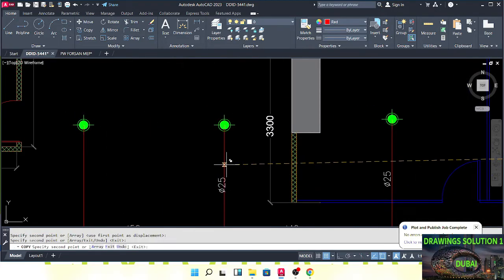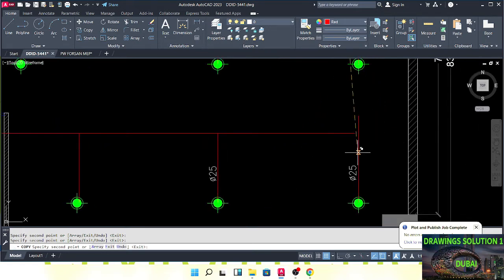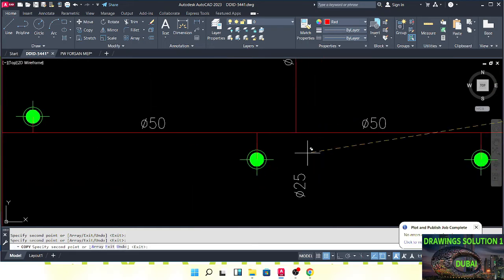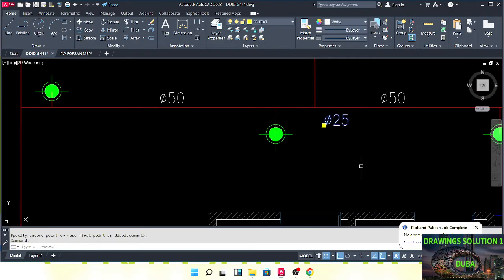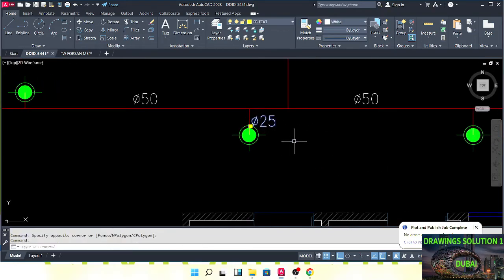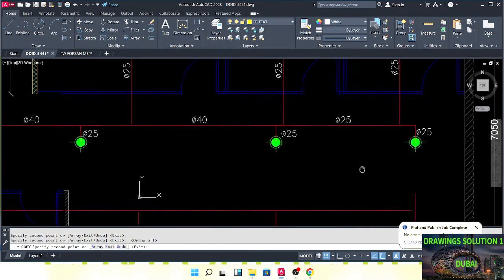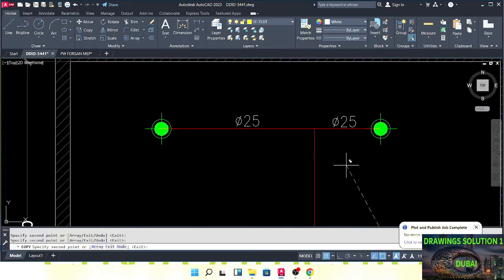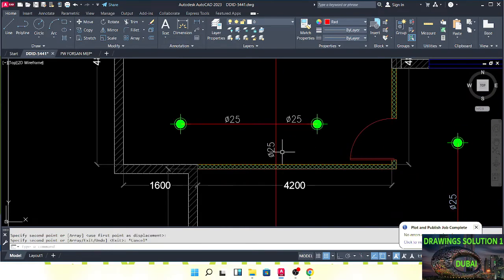We can write down: single sprinkler pipes will be 25mm, 25mm, 25mm, 25mm, 25mm all around. This pipe size should be 40 because we have more than three sprinklers — so this dia will be 40, as it is serving four sprinklers.